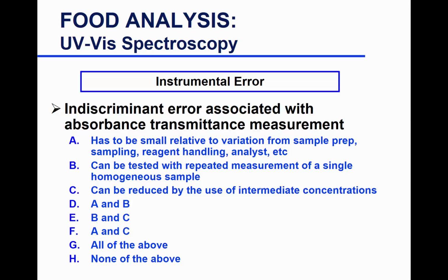to make sure that you have a correct reading. So as a rule of thumb, we say 0.2 to 0.8 would be great. If you make sure your sample is diluted so that you get absorbances between 0.2 and 0.8, that is good. But this is just a rule of thumb, because there are different components that will have a wider linear range than others, and an absorption of 1.5 will still be acceptable for some.